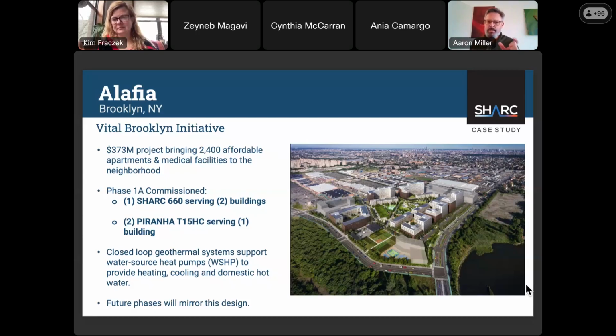By putting the SHARC into the loop, and this is wild, only picking up the peak cooling loads from those 5, 6, or 7 really hot days allowed them to right-size the bore field from 125 down to 93. That's about a $500,000 to $600,000 first cost savings, right off the top.